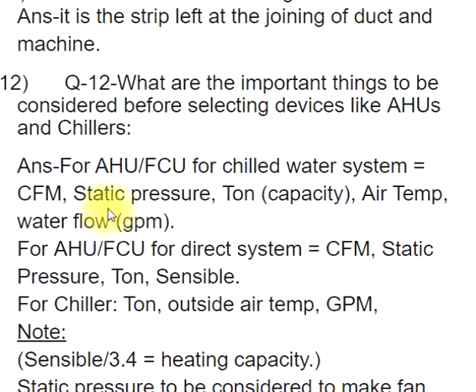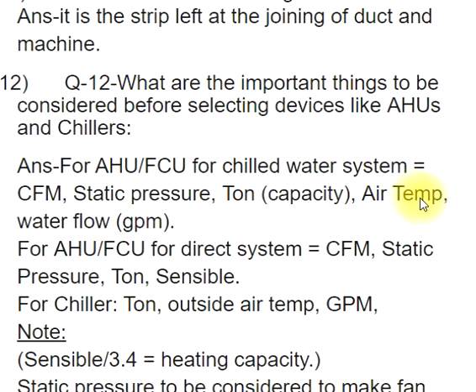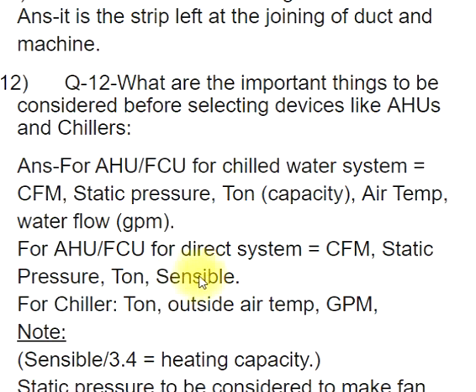Q12: What are the important things to be considered before selecting devices like AHUs and chillers? ANS: For AHU/FCU (chilled water system): CFM, static pressure, tonnage capacity, air temperature, water flow (GPM). For AHU/FCU (direct system): CFM, static pressure, tonnage, sensible. For chiller: tonnage, outside air temperature, GPM.